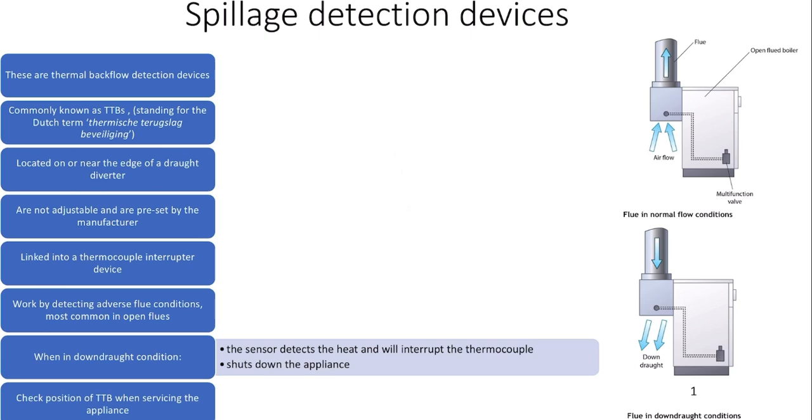They work by detecting the differences in heat under adverse, that means bad, flue conditions. When a flue is spilling in downdraft conditions, the sensor detects the heat and will interrupt the thermocouple system. This, in turn, shuts down the appliance.